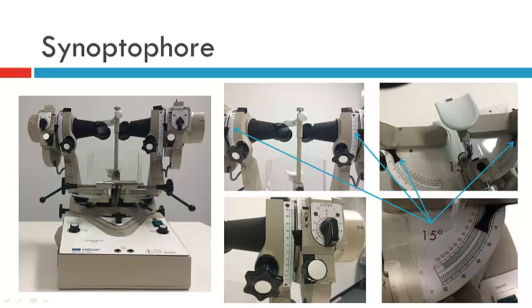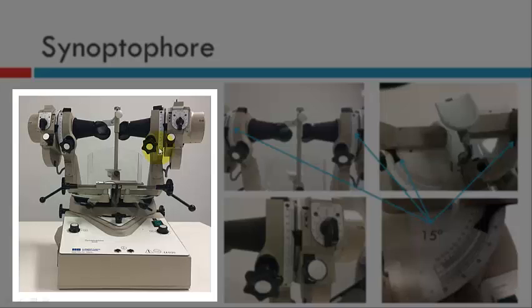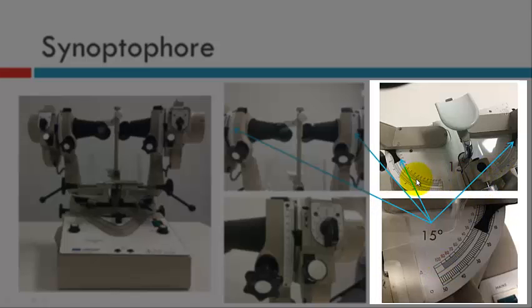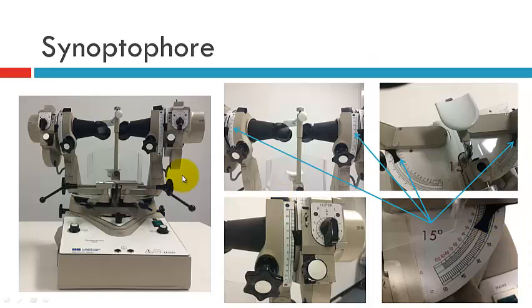Let's look at what it looks like when the tubes have been moved. In this photograph the synoptophore is moved to the right and up — you can see the tubes are elevated. Looking more closely, you can see we've placed the tubes at 15 degrees up here, indicating the patient is in 15 degrees up gaze. For the horizontal component, both the right and left levers have moved into 15 degrees, so we're assessing the patient in dextral elevation.